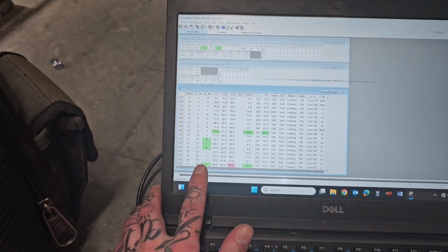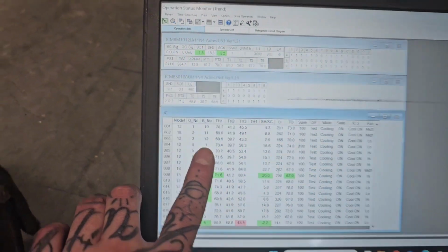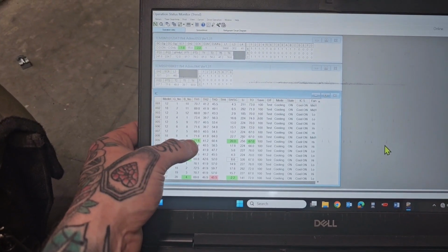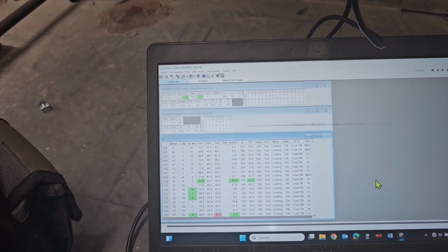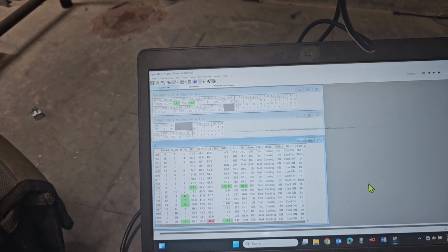Okay? Now why we have to do that is because you see this unit is on port 1, and we also have another unit that's on port 1. So how does the branch controller know, okay, we've got 2 port 1s calling for cooling? Well, which ports do I open on the branch controller? Because we have 2 that are supposedly saying that they belong to port 1. We can have up to 3 units on the same port, that's fine. But if you're not designing that way, then it's not going to work correctly.